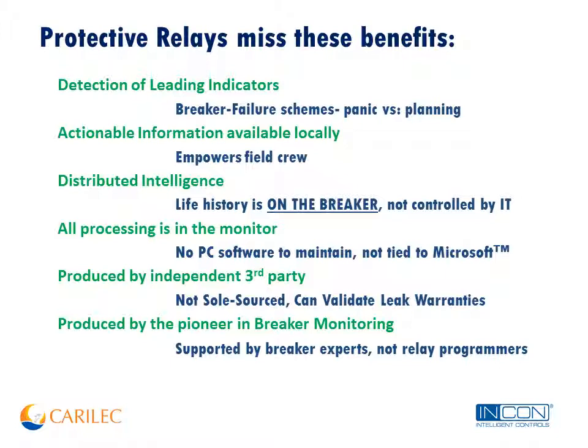Okay, so Incon is an independent third party compared to breaker manufacturers and protective relay manufacturers. So we're not a sole source, and a third party can honestly give you leak warranty validation. If you're looking for a 0.1% leak rate out of your circuit breakers, and that's what the warranty says, you can know with certainty whether or not the warranty is something you need to look into. Say you're leaking, and you can check up on these manufacturers and these claims.